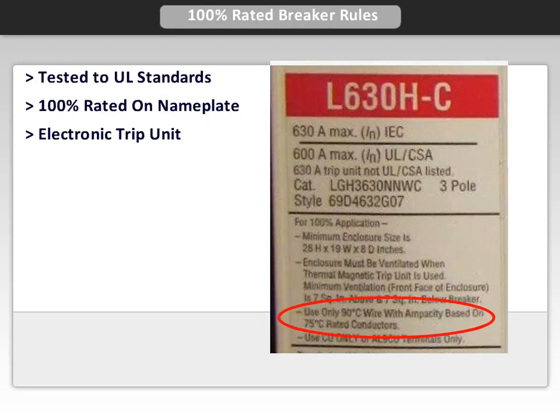The next rule may seem a little confusing: only 90 degree wire may be used, with ampacity based on 75 degree rated conductors. Using 90 degree rated wiring provides a more robust insulated coating. Using the ampacity at 75 degrees provides additional cooling because of the lower current. Effectively, you are derating the wire.